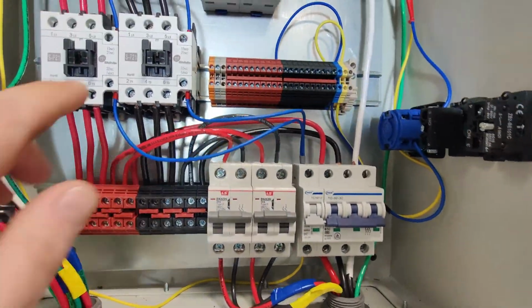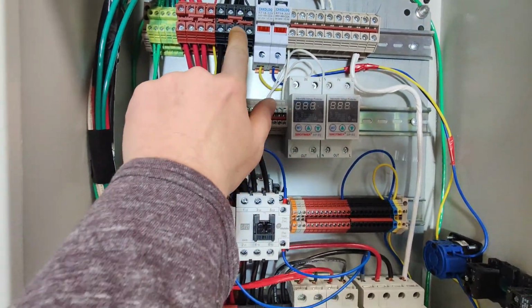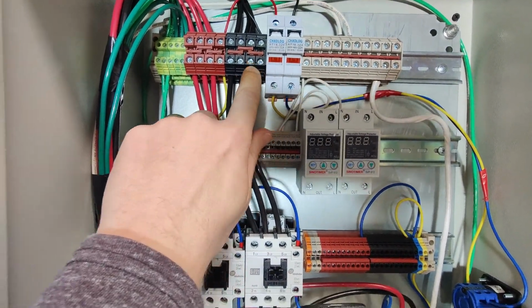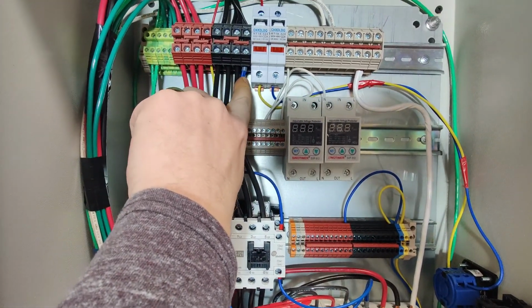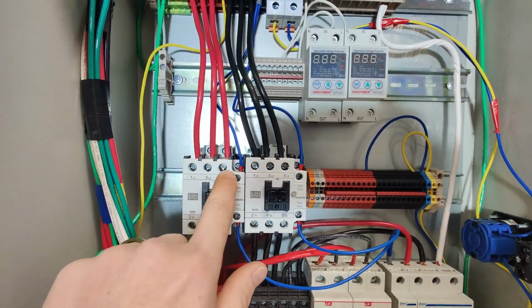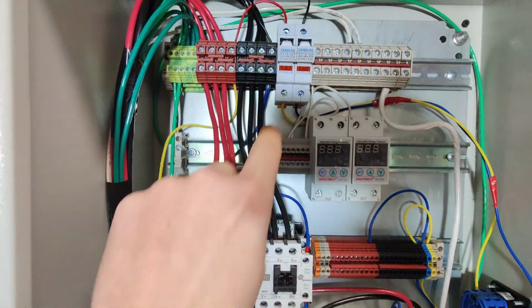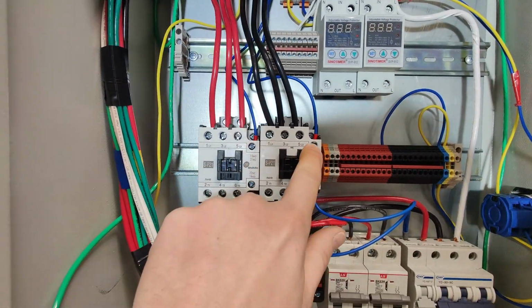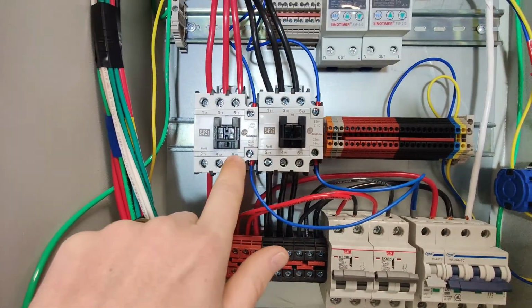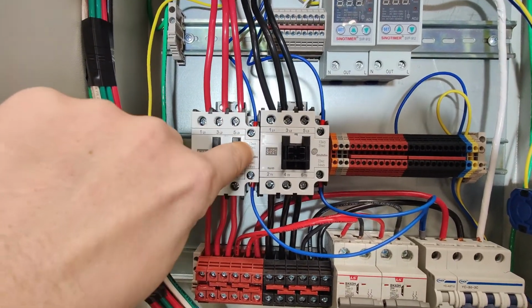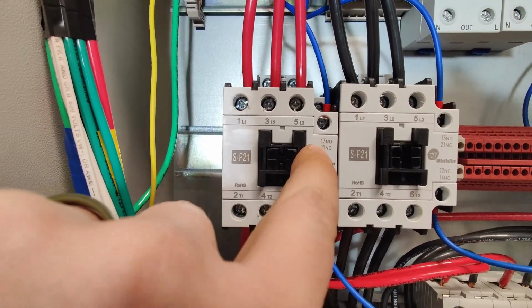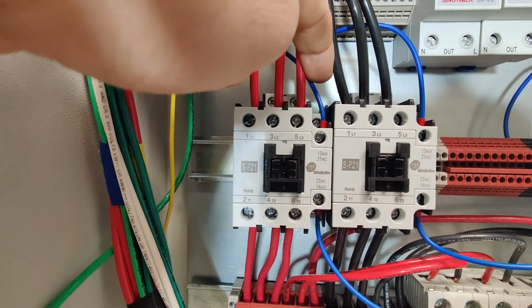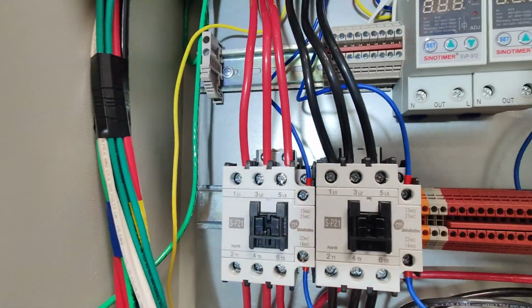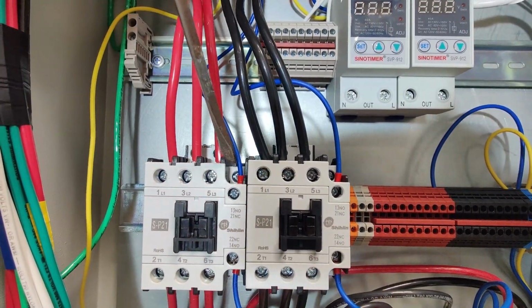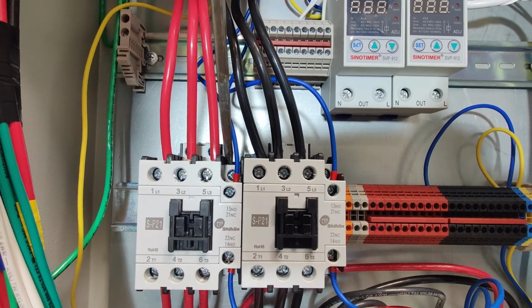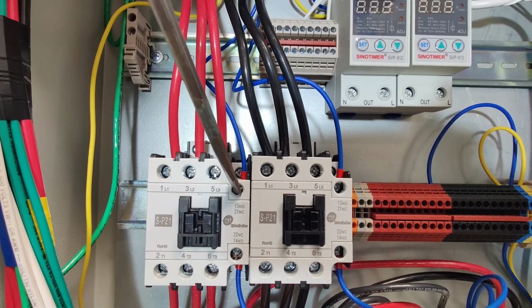Okay, so now we have a wire coming out of the other hot leg, and that wire is being split here at this cable, and it's going to both contactors. So it's coming out of one hot leg, going into the normally closed side of both of these contactors, and the normally closed is the top side. So you can see right in here where it says NO, NC, NO being this one back here. Get a pointer. That's this one. The NO side is this one back here. The NC side is this one up here.